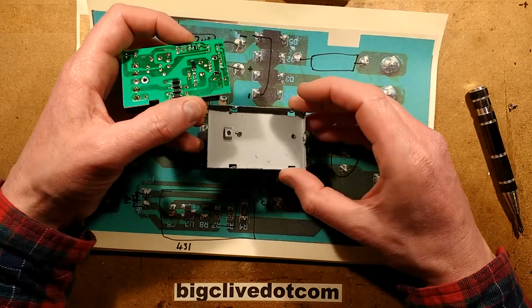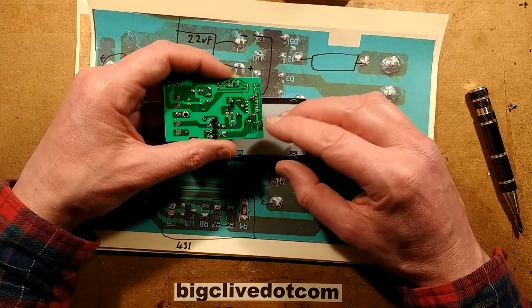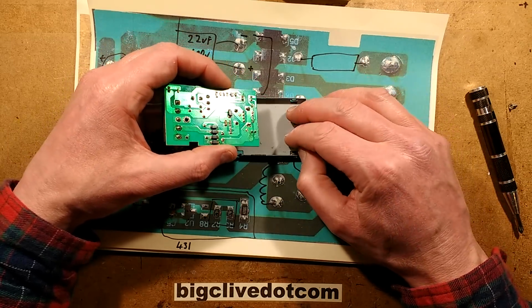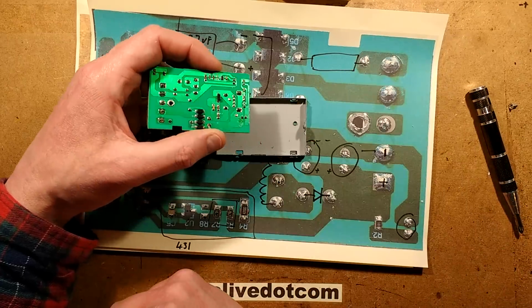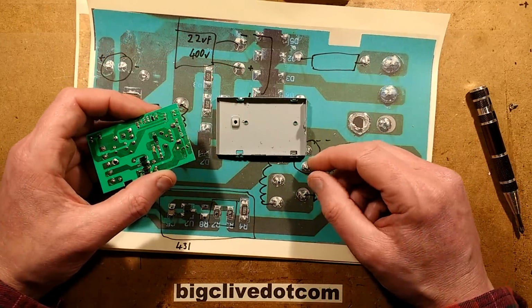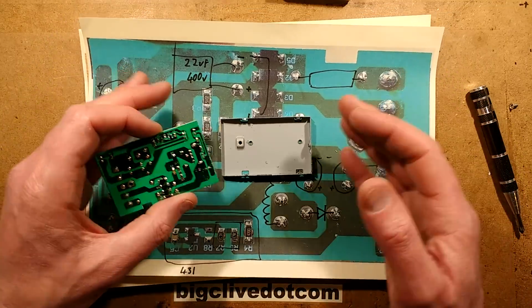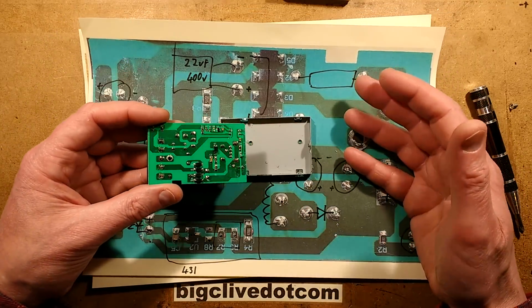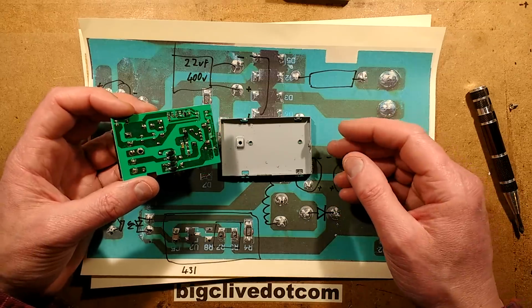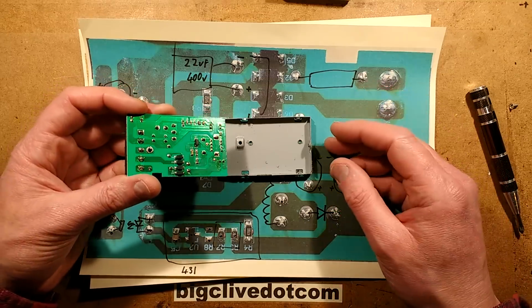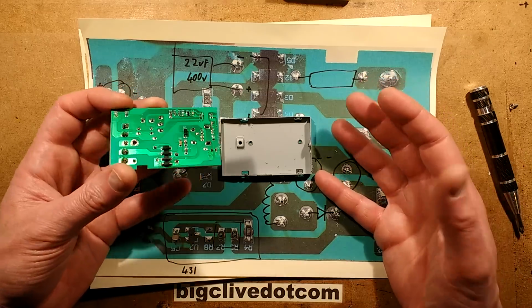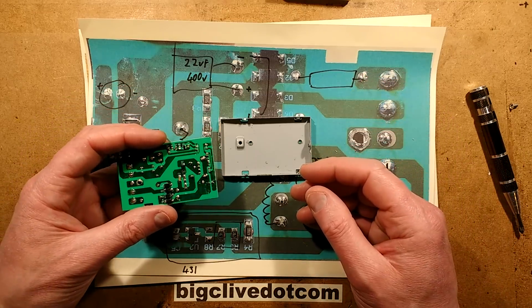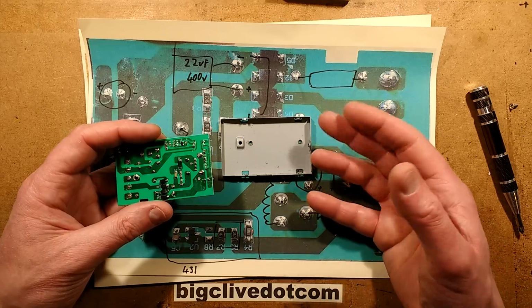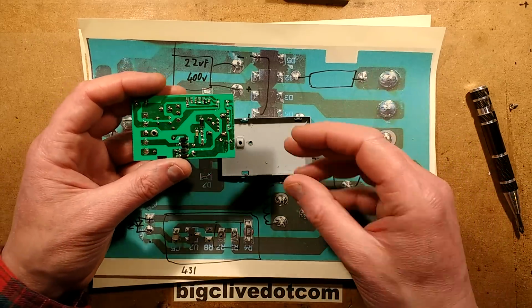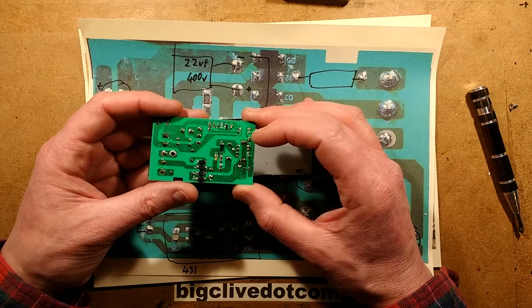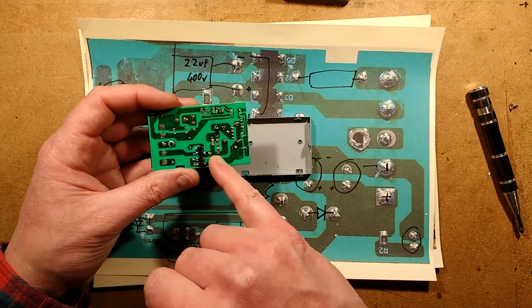I'm not sure what that was, something was making a hissing noise. Given that it's AC, it might just have been coupling through the plastic. That test was a bit extreme though - over 1,000 volts from live and neutral to earth, because normally in the electrical industry the maximum you'd test is about 500 volts, and supposedly in the IT industry it's supposed to be 250 volts maximum, which is a bit pointless because at 250 volts that's not representative of the peak mains voltage in the UK in the first place. The other notable thing is the snubber network they've got across the back of the coil here, with a couple of resistors, a capacitor and a diode.